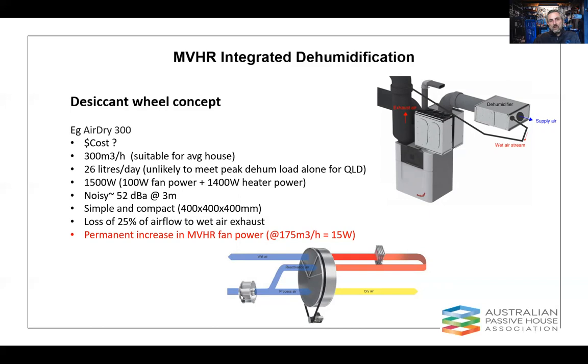There's about 100 watts of fan power, but that heater there, because we've got to get that air temp up on that discharge area, is about 1400 watts. So there is some reasonable power consumption. Also not particularly silent, so most of that will be fan power noise in there, so we just need to be a little bit careful about where that's positioned in relation to being a nuisance.